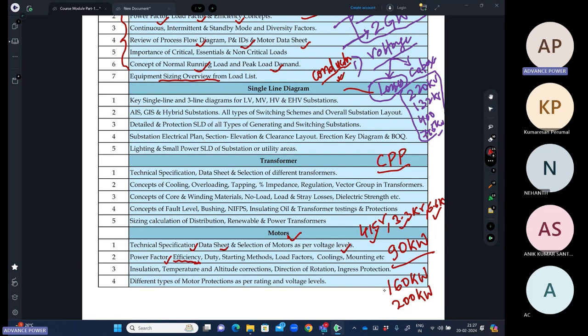Again, if I am selecting a motor, which efficiency level do I have to choose? So again, we do a cost benefit analysis here: whether taking a loss is better or paying an upfront price now is better. We'll do the NPV calculation for the losses we will incur over the lifetime of the motor. Then we will be able to say that this motor is suitable for efficiency class 2 or class 1 or class 3 accordingly.